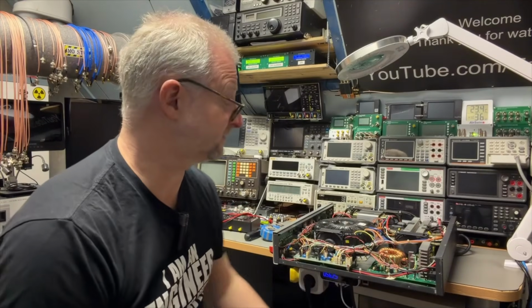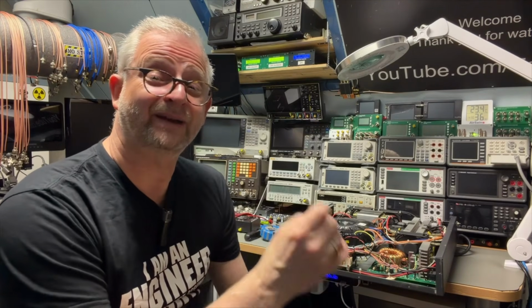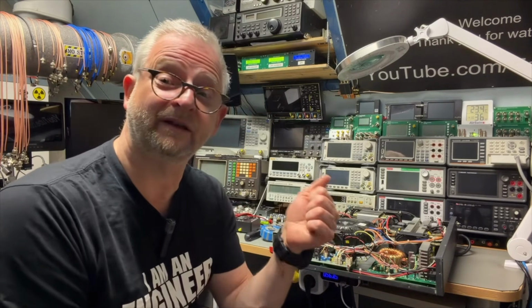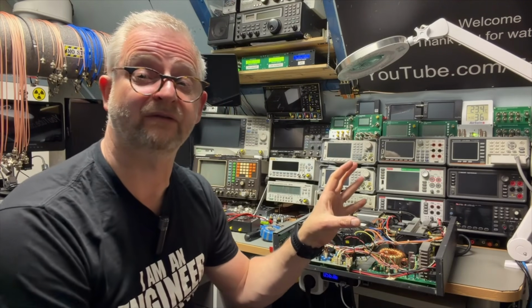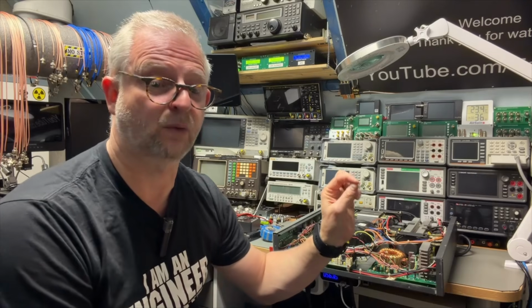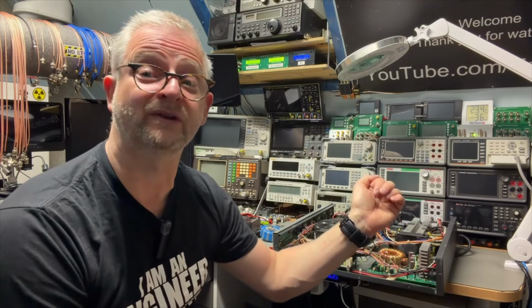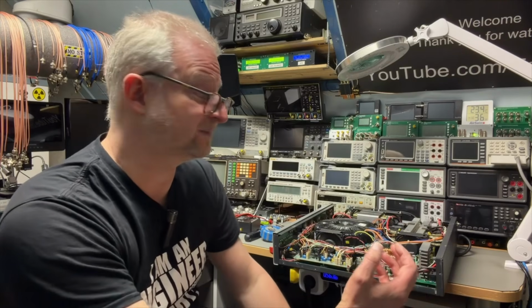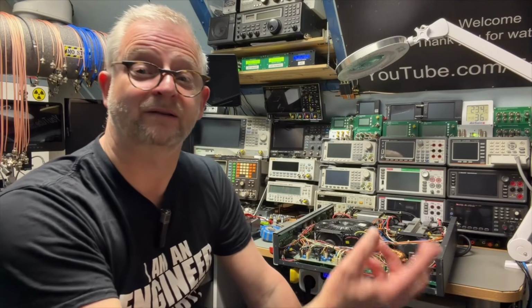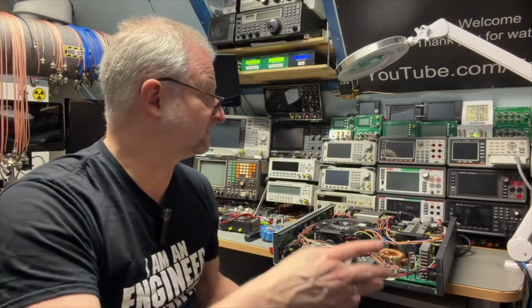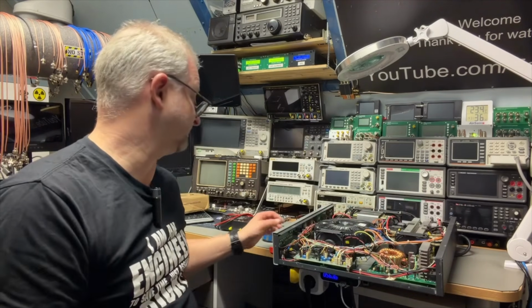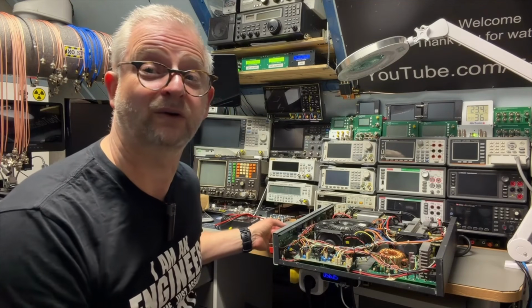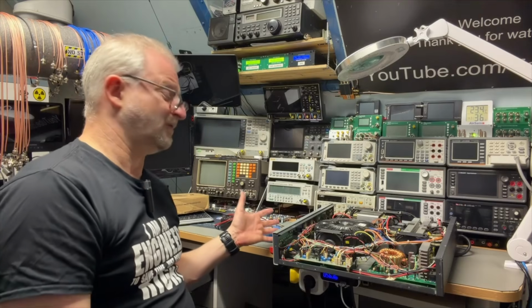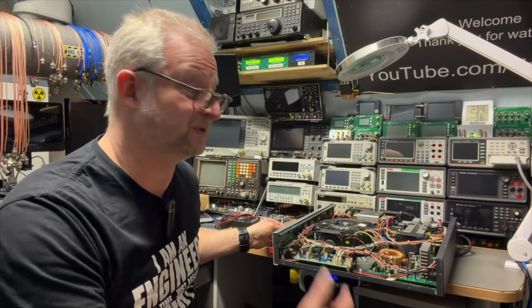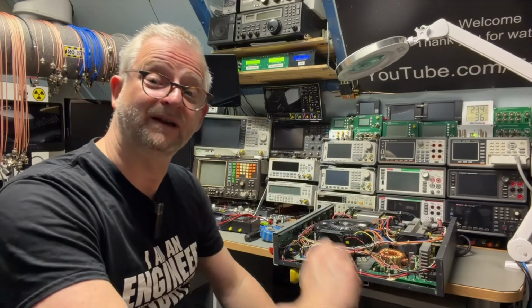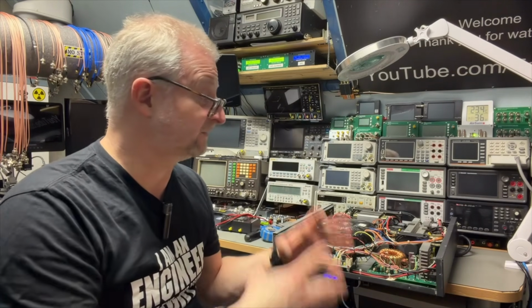A few little things I need to look at. The relay is very closely matched to its maximum because it can switch 16 amps at 250 volt, and about 20 amps at 125. The voltage is only up to 35, so maybe it can do a little more than the 20 amps. Probably they used two contacts in parallel, so it can do this 40 amps, but that's exactly at the limit. Also, the manual says don't switch the output on and off under load, but that's exactly what the button is usually for. You can set your voltage and current, and when you agree with it, you switch the output on, so that means you always switch with load.